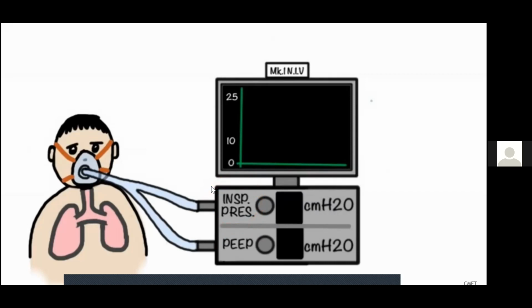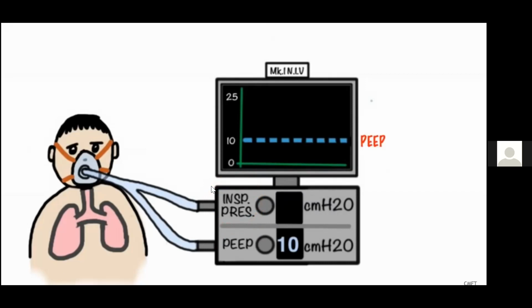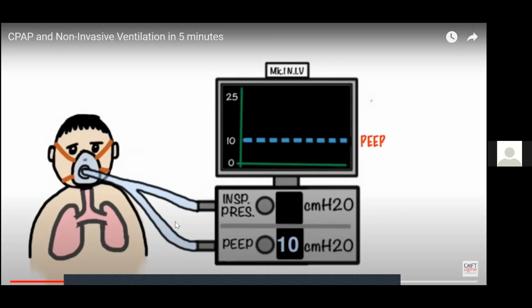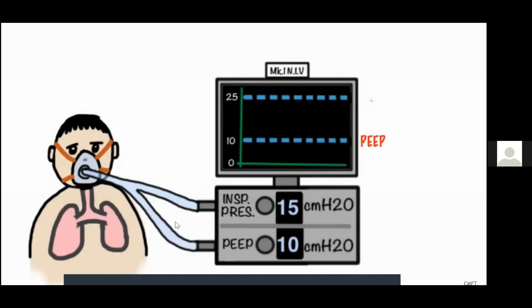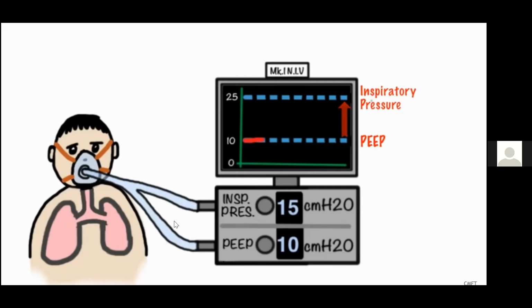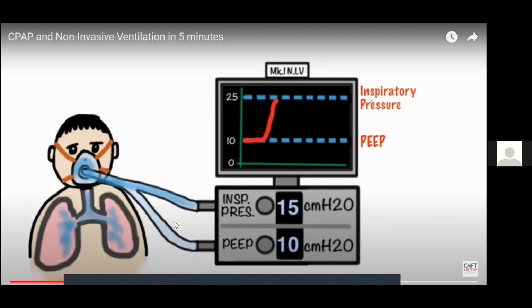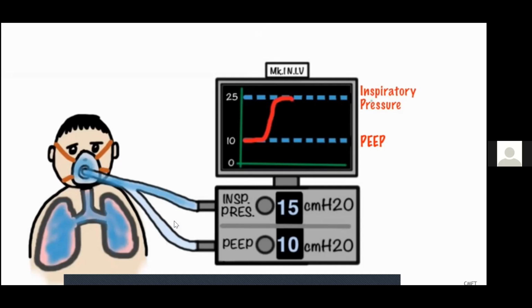So let's assume that we set the PEEP at 10 centimetres of water. The pressure in the patient's lungs will not drop below this level. It's now the baseline pressure, if you like. Now assume we set the inspiratory pressure at 15 centimetres of water. Note that the inspiratory pressure is added on top of the PEEP. As the patient takes the breath, it causes the ventilator to initiate. It now increases the pressure until the inspiratory pressure is achieved.